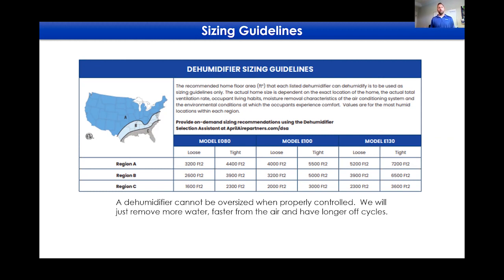Most of these dehumidification systems—at least I can speak to the Aprilaire brand—have a test. If it doesn't run in an hour, we'll turn the fan on and measure the condition of the air coming in. That way we know if we've done our job, and can shut off for another hour to save energy, or if humidity is creeping up, getting drawn into the unit, and we go ahead and dehumidify.